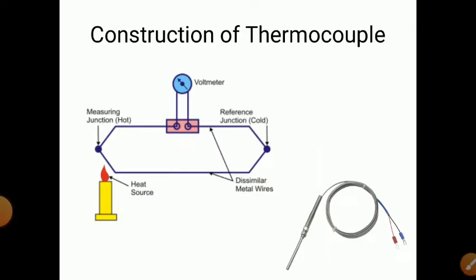First, you should understand what a thermocouple is. A thermocouple is made up of two dissimilar metal wires connected together such that they form two junctions. One junction is called the hot junction and the second is called the cold junction. The hot junction is where we are going to measure the reading — it is also called the measuring junction. It works on the principle that as a temperature difference occurs between both junctions, a voltage is induced in the circuit.